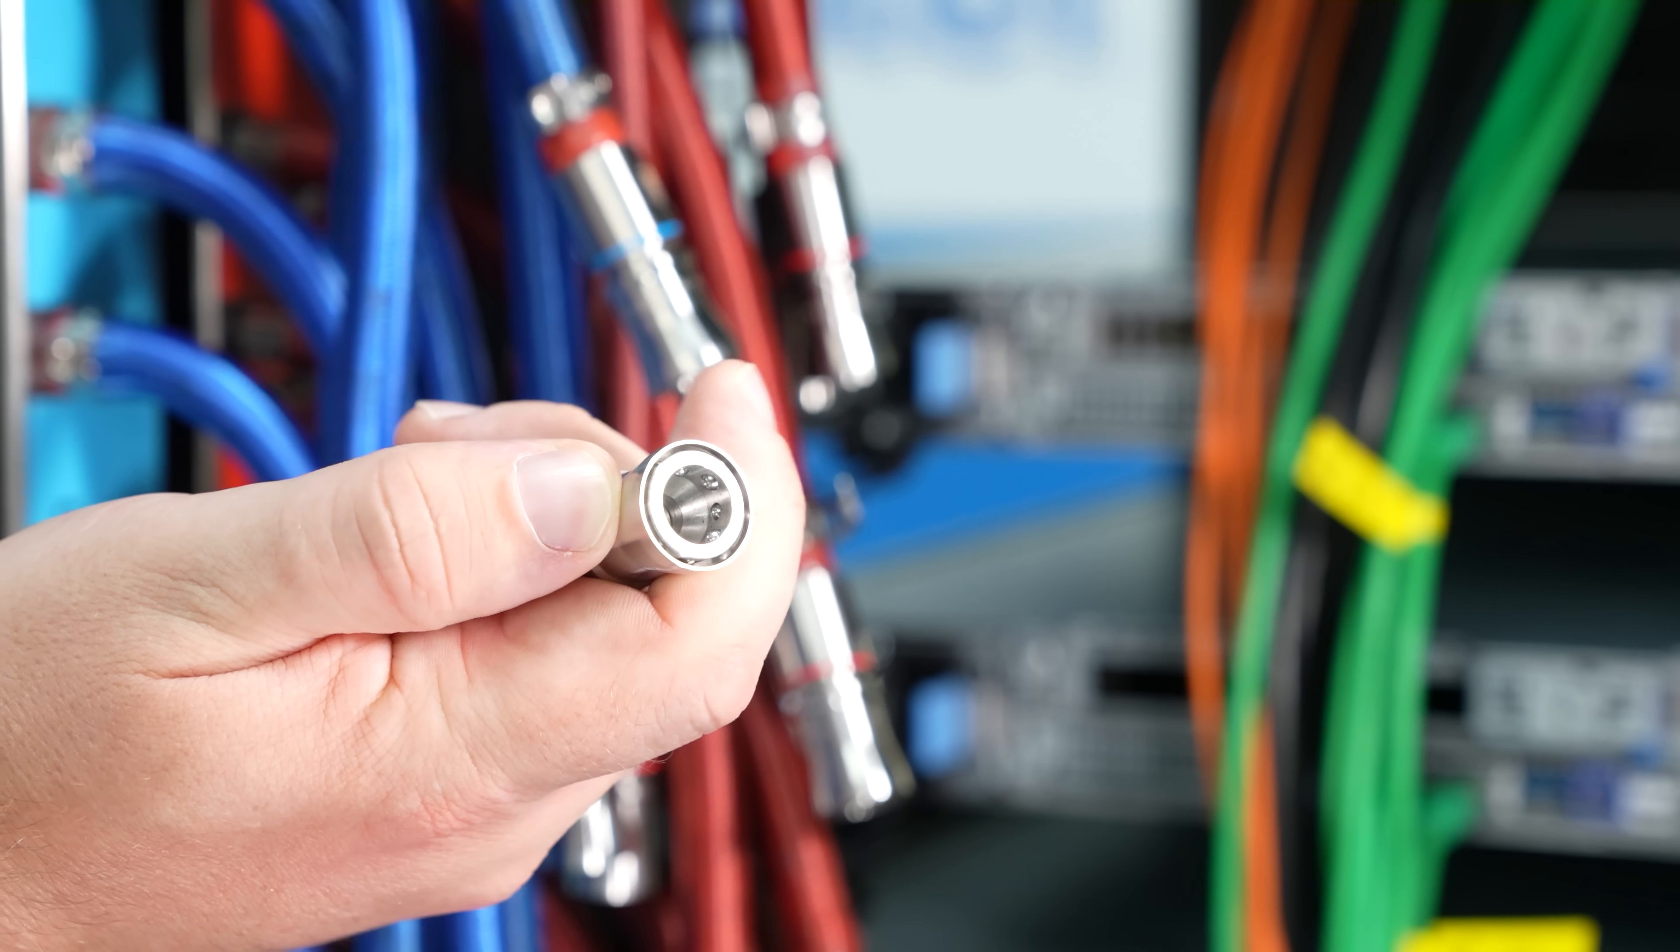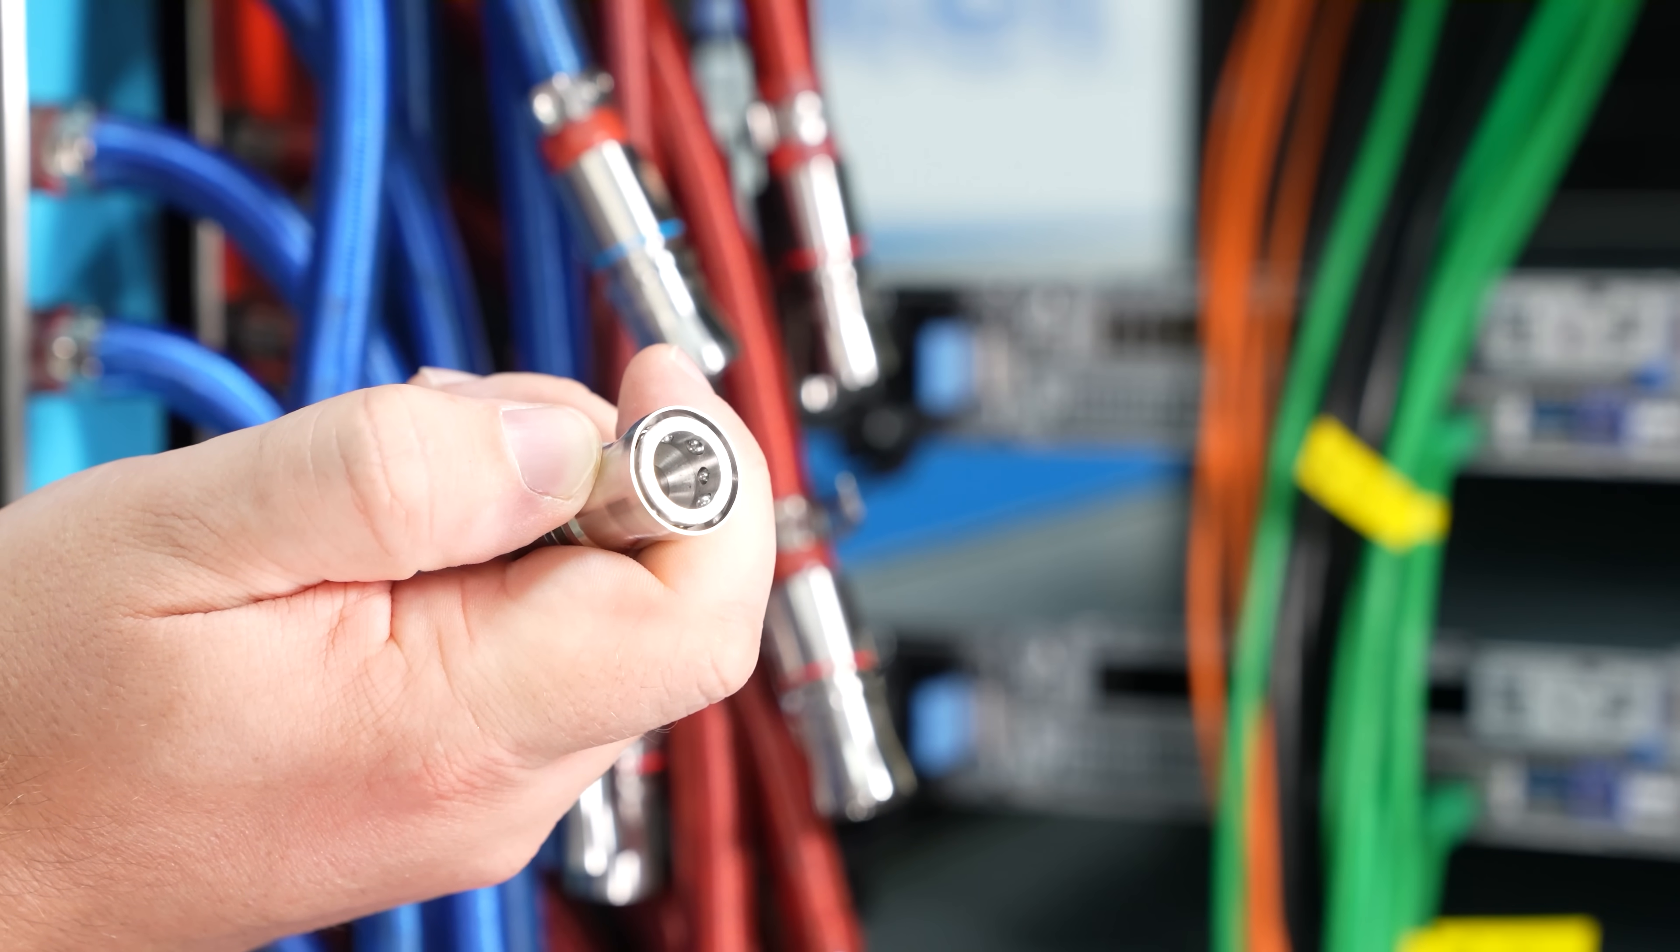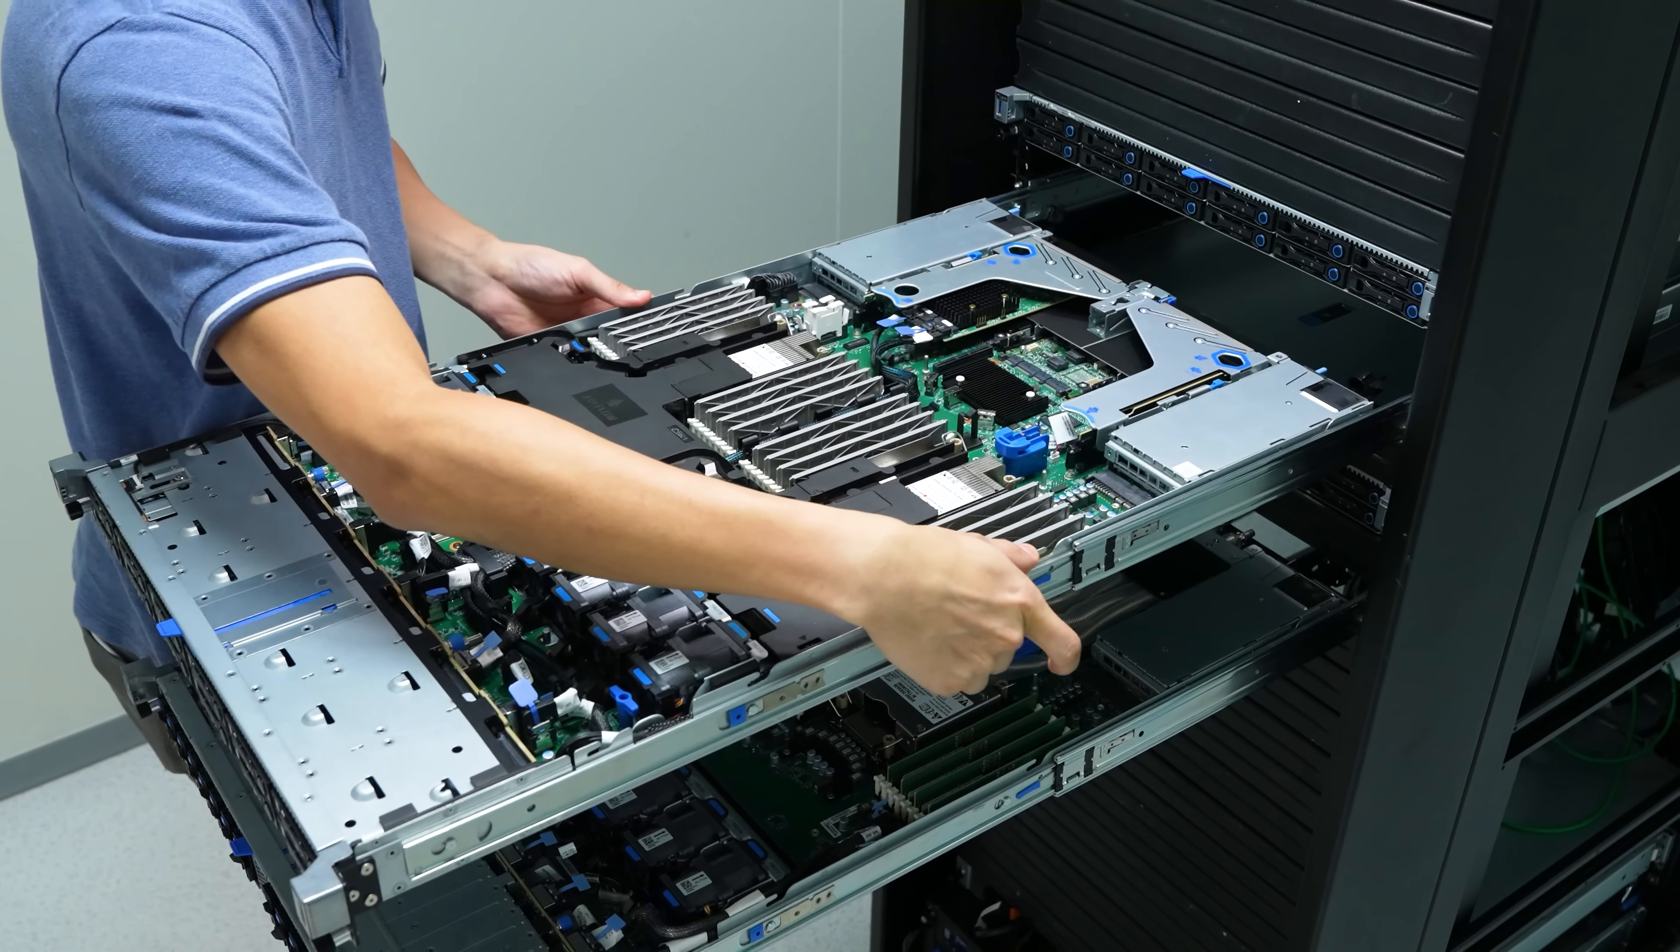Now, something that you're definitely going to notice here is the fact that this is not set up for just four servers. This is set up for an entire rack of servers. We just have four for our little demo here. And in case you're wondering what the difference is between blue and red, blue means cool, and red means hot, and that's pretty universal in all of the liquid cooling systems that we've seen. As you would expect, all of the fittings are quick disconnects, so you're able to go and pull them out and not have like a whole bunch of drips and like leaky fluid or something like that. Instead, these things just kind of, you know, you pull them out, and then you pop the server out, and you're ready to go, and there's not like liquid flying everywhere.